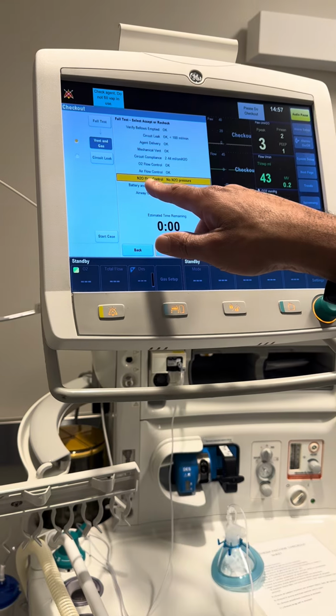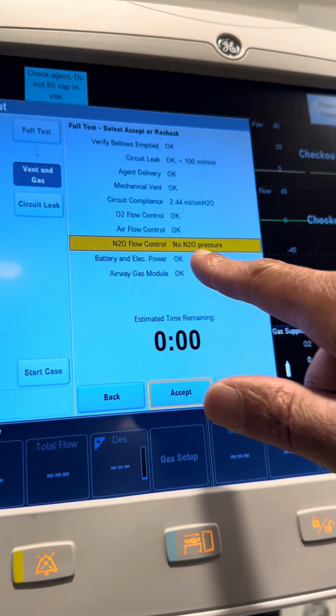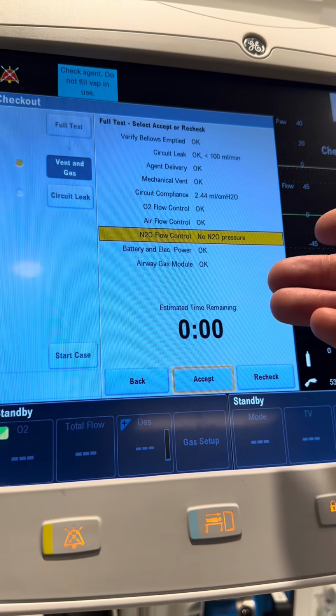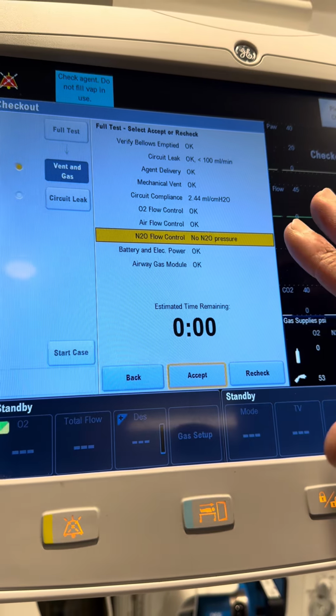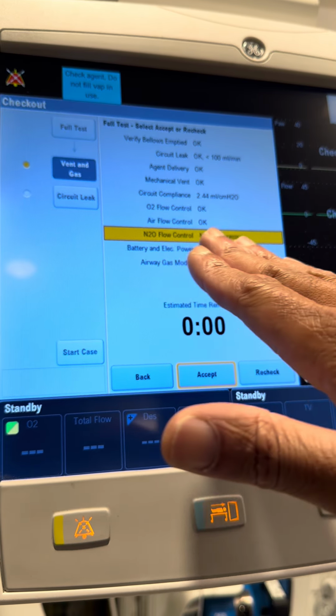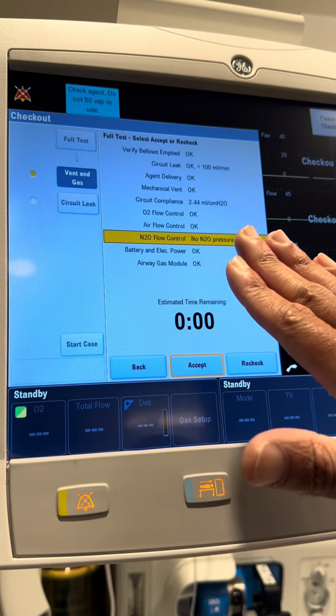Okay, and you see we have an error right there where it says N2O flow control, no pressure. That's because we don't have any nitrous oxide going from the wall. So that's okay, that's good to go. But in the normal setting, this would say good to go, and it'll say okay. So don't worry about that, I'm good to go.